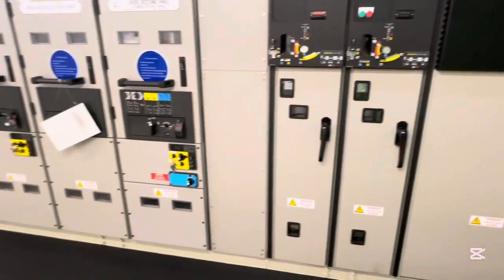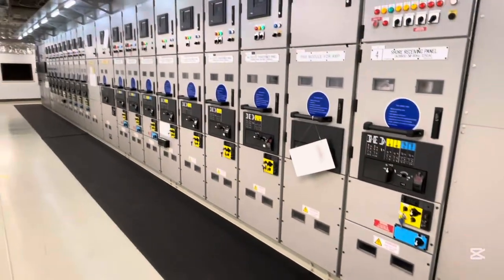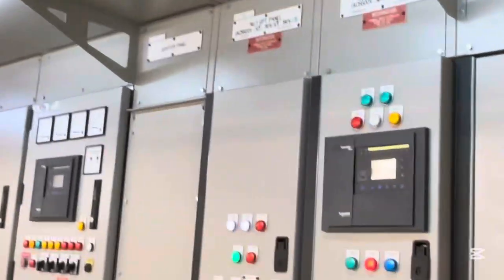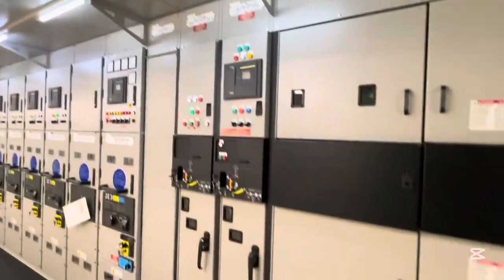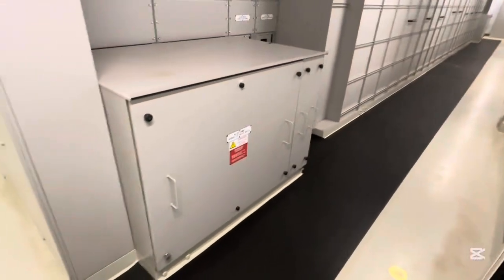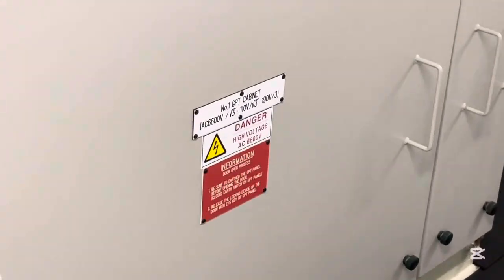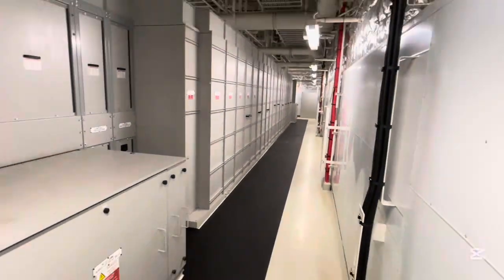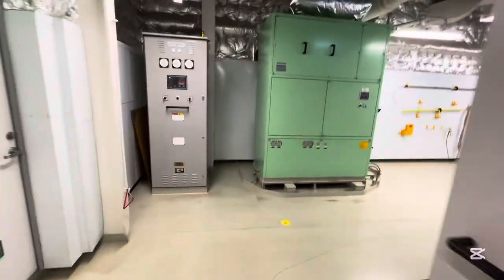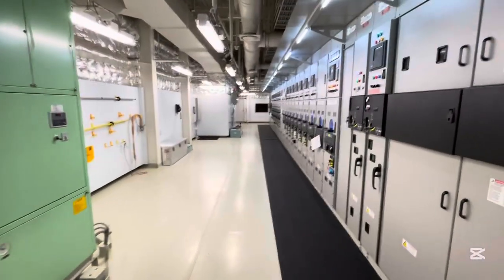And other than that, you see there is something called GPT. As I mentioned earlier, in the books we studied, low voltage ships use an insulated earth system, whereas high voltage ships use an earth neutral system, so earthing is done via neutral earthing resistors - that is what I studied in Elston Fernandez's book. But on my ship there is no NER; rather it is by GPT, that is ground potential transformer. So basically this is the earthing of my ship - we have a transformer for it.